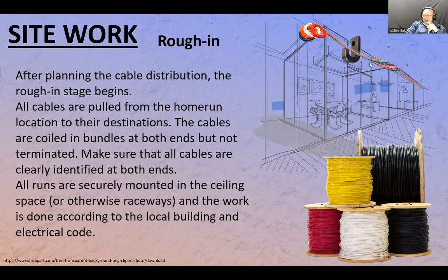So bundle them up as much as I can. And that takes a little bit of planning, looking at the drawings, see, okay, if we pull everything to this point, we'll be able to service this jack and this outlet and that outlet and maybe something in the ceiling here. So this will be a good common point. All right, so let's do it here. And from here, we're going to fan out with those wires. But from here to here, we're going to have one main bundle.